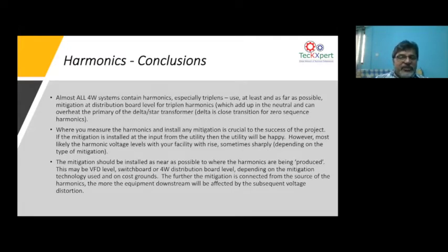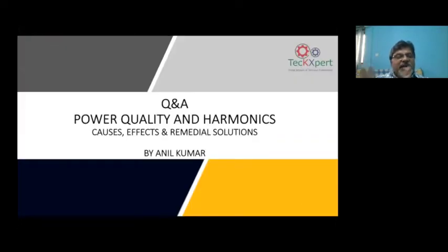Again, active front-end, active filters, if you look into all, you can have three-phase, three-wire systems and three-phase, four-wire systems. All these sort of applications are possible with active harmonic filters. So you need to select which type of filter you need to buy. If you have a lot of non-linear loads like lighting loads, you should select a four-wire system rather than a three-phase, three-wire system. Also, you should do proper measurements where you measure the harmonics, and this is crucial before installing any mitigation. Don't select and install filters without proper harmonic studies. The mitigation should be installed as near as possible to the harmonic producing load, as I said before. The next slide. Yeah, that's it.